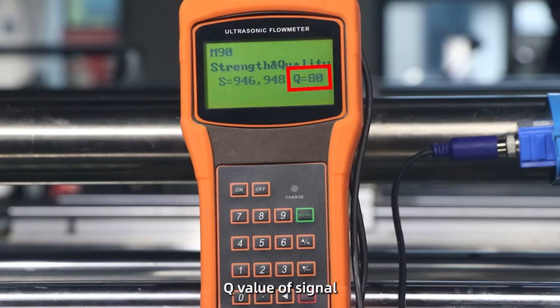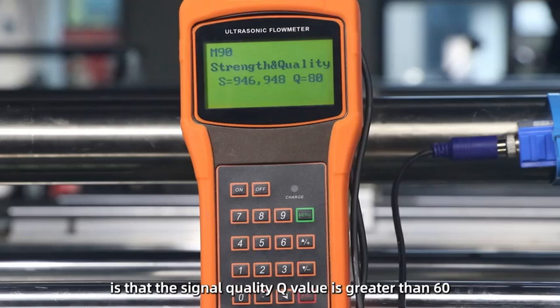Q value of signal quality is represented by numbers from 00 to 99, with 00 being the worst, and 99 being the best. Generally, the normal working condition is that the signal quality Q value is greater than 60. When installing, please pay attention to adjust the sensor to make the signal strength and quality bigger, so as to ensure the long-term stable operation of the Flowmeter and make the measurement results more accurate.